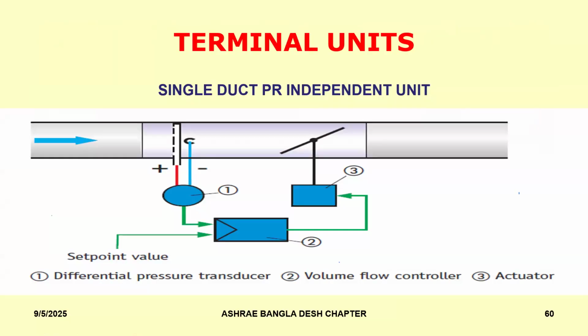These are generally used with all mixing air systems, where it's nothing but a damper, but the damper is getting an input from two sources. One is it can get an input from a set point. This set point could be the room temperature, or the room CO2, or the room VOC, right? And it is also getting an input from the actual amount of air that is flowing through the space. And then, based on the kind of programming that you feed into it, it will allow the exact amount of air that is required to meet your set point value.